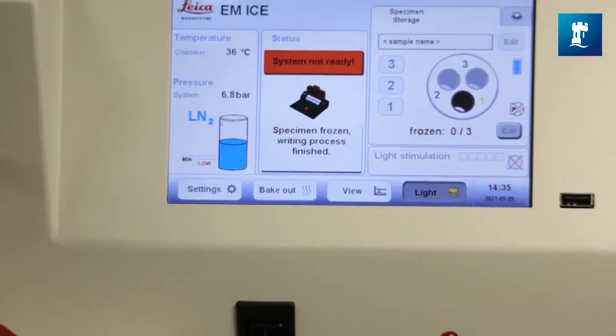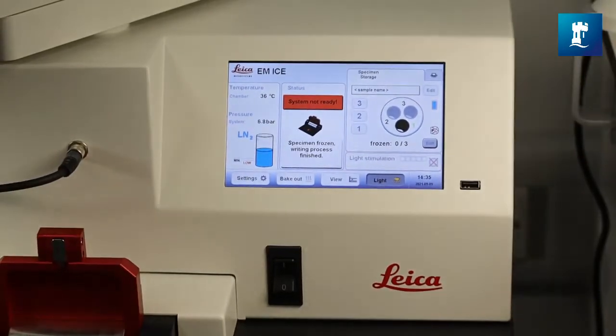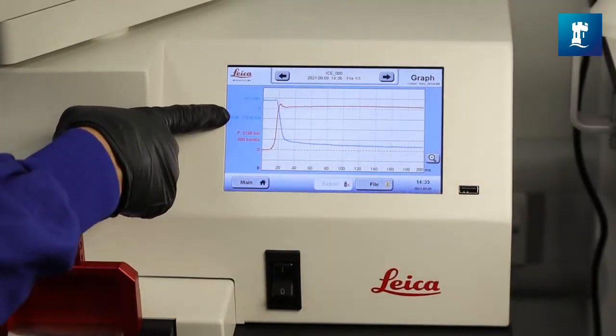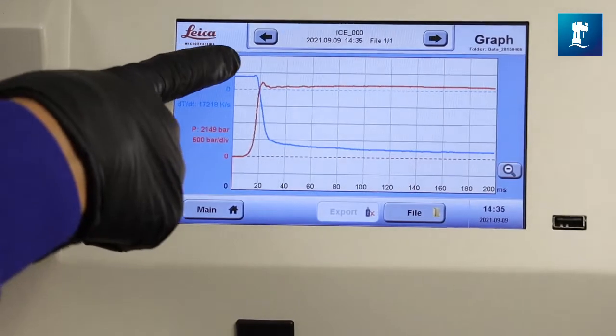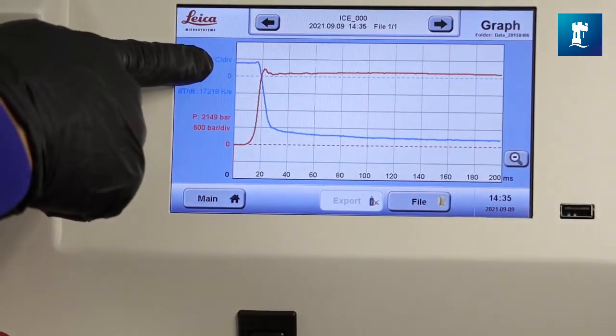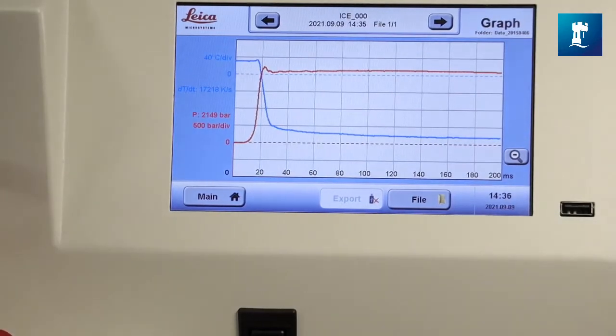Freezing cycle performance is monitored by the instrument and you get a readout in the form of a graph which shows you the change in temperature and the change in pressure over time. These two should intersect at zero and the value of dT over dt should be greater than 15,000 and then you know that you've got good system performance.